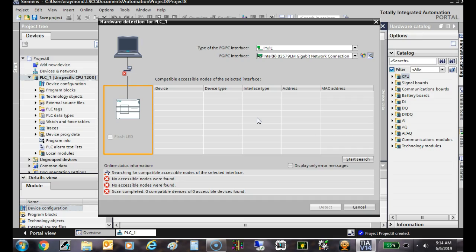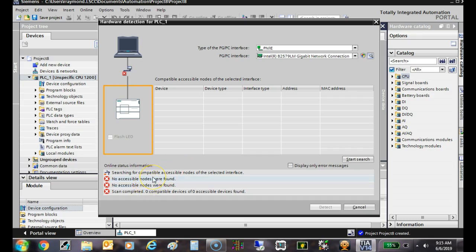I'm not getting any lights. The green one is the link light - it should stay on solid all the time, indicating that you've got a connection to your PLC. Then the yellow light will start blinking because that's the data transfer light. When I look at my computer I get no blinking lights, which probably means what?